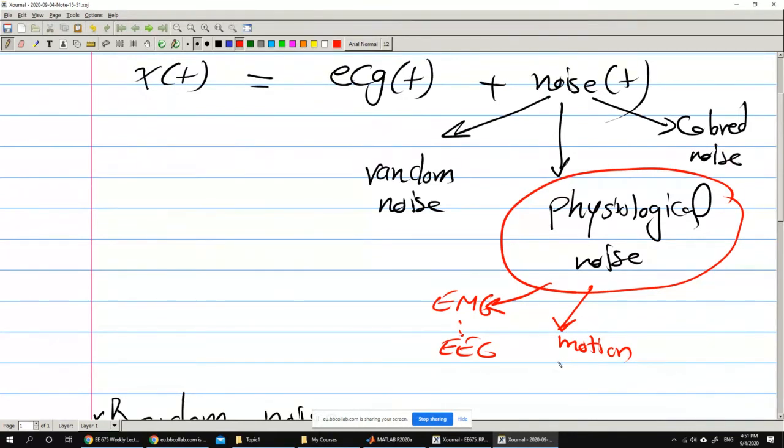So it changes the magnitude of the signal depending on the motion, which causes an artifact where in certain locations the intensity is higher, and in certain locations the intensity is lower. So you make changes to the ECG signal that are not dependent on the actual signal that comes from the patient. This is a big problem.